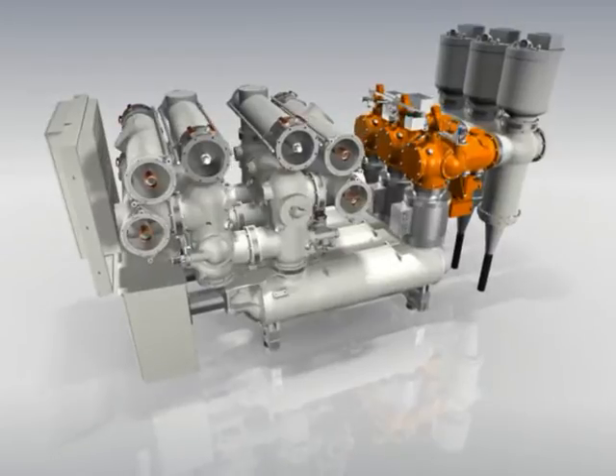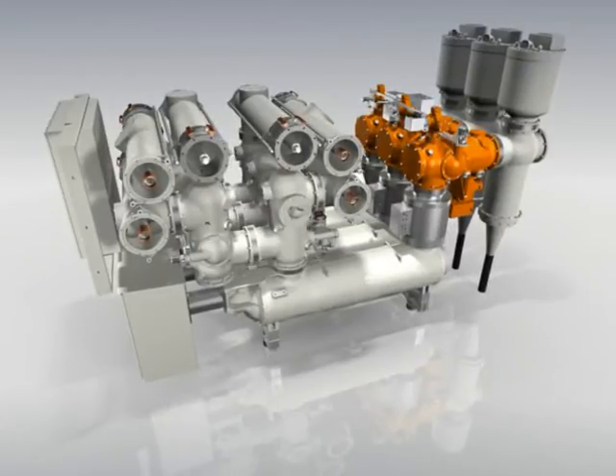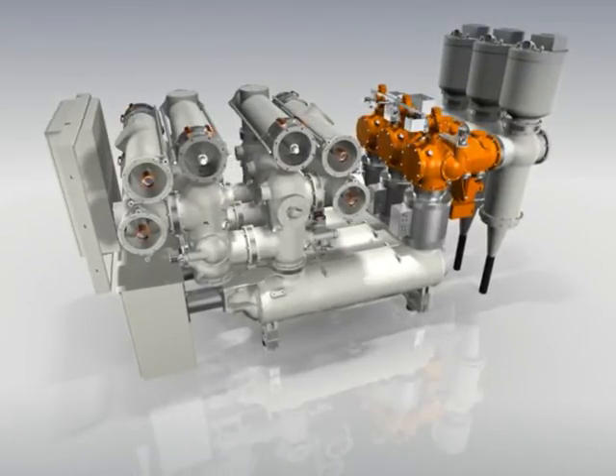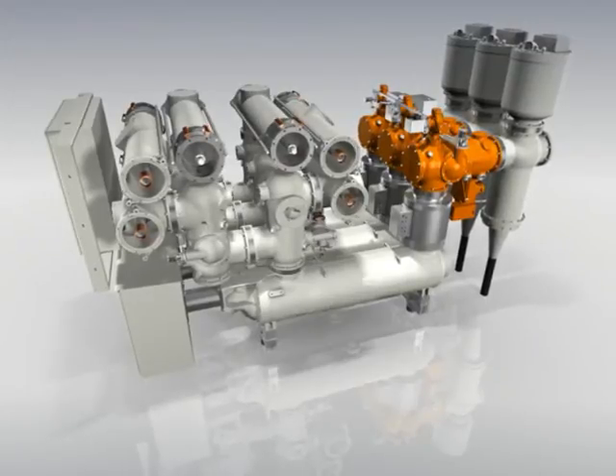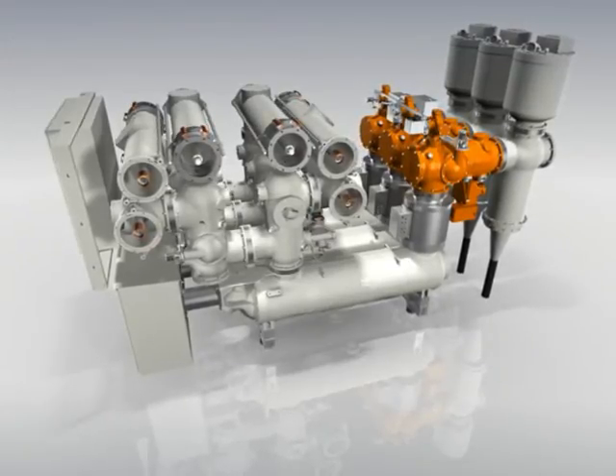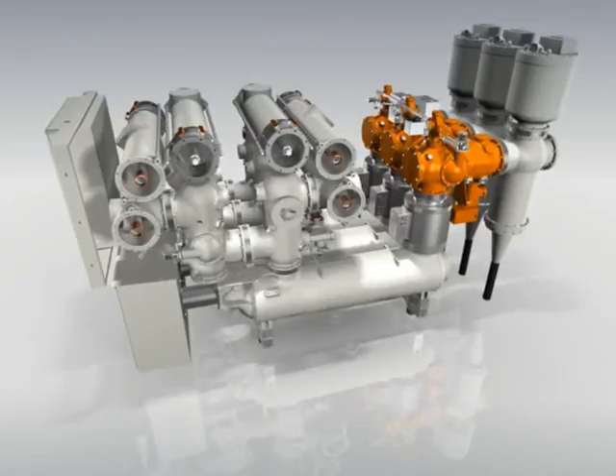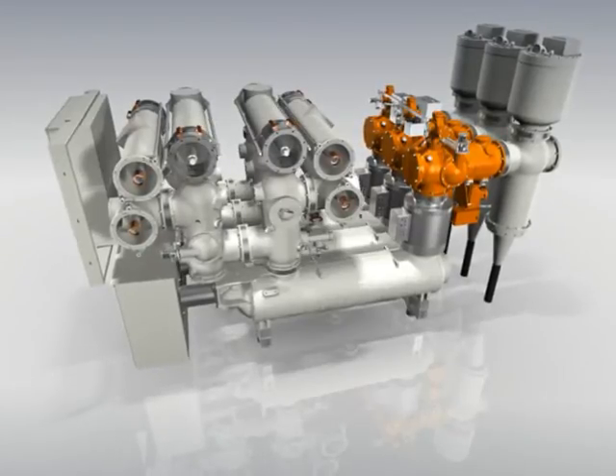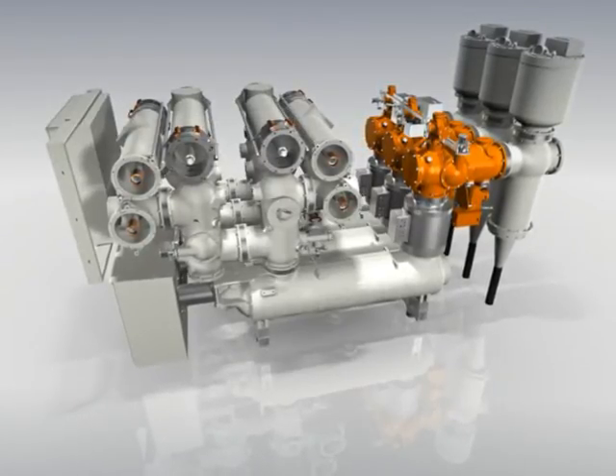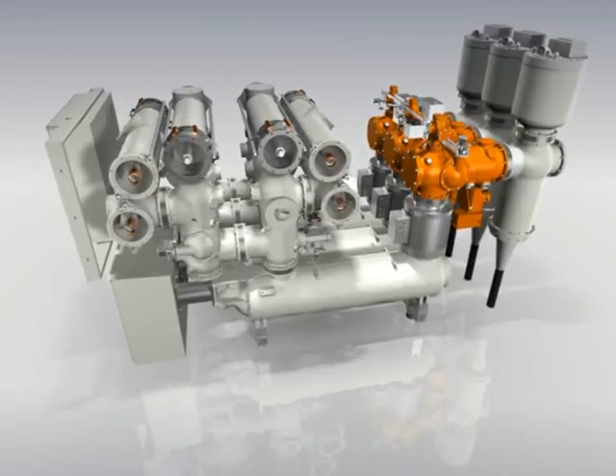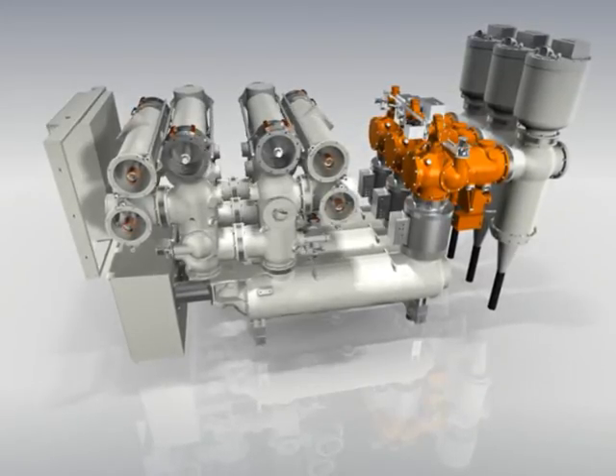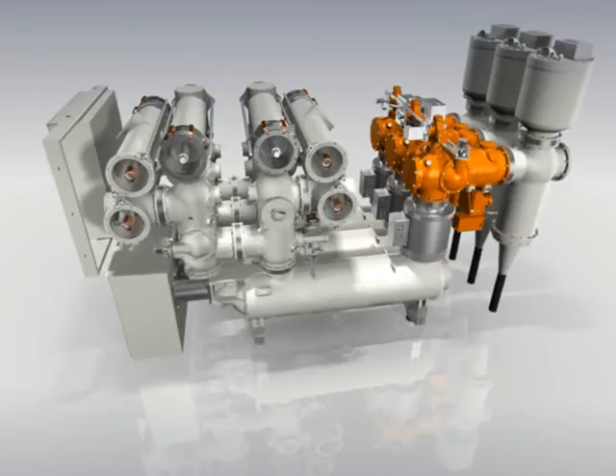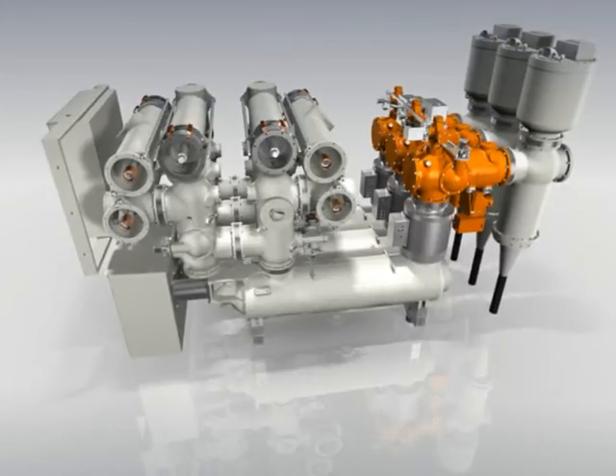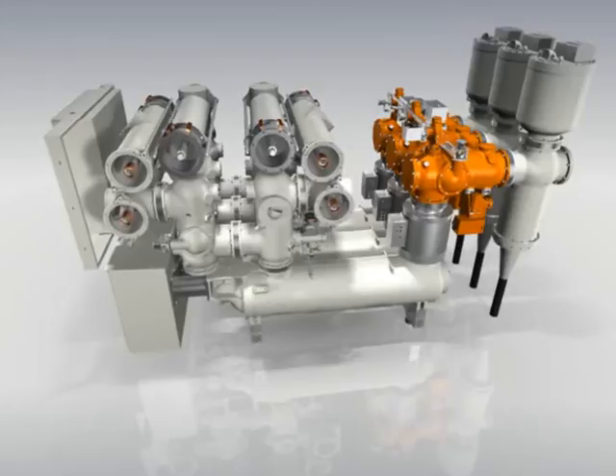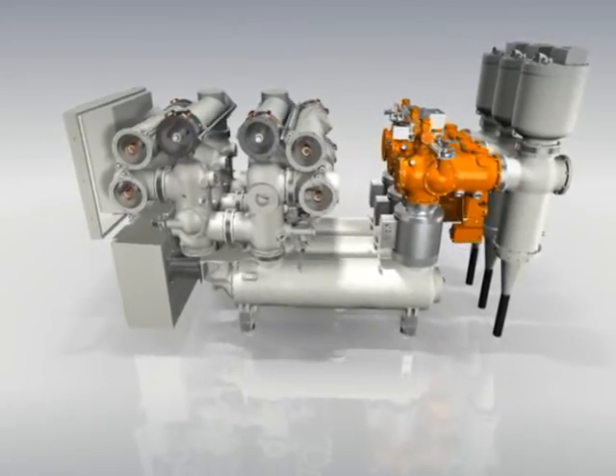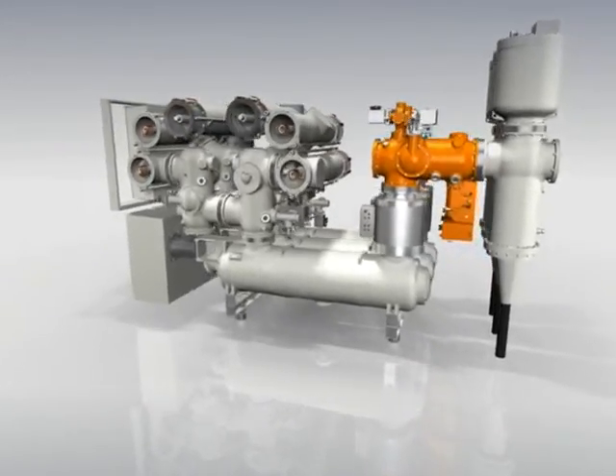Disconnecting and earthing are integrated in one multifunctional module, which is used for busbar switching as well as for cable, overhead line, and transformer termination. Earthing and short-circuiting system components like overhead lines, cables, and transformers after isolation can be performed through either a working earthing switch or a high-speed earthing switch. Thanks to large viewports, the position of either the disconnector or the earthing switch is easily visible in any case.